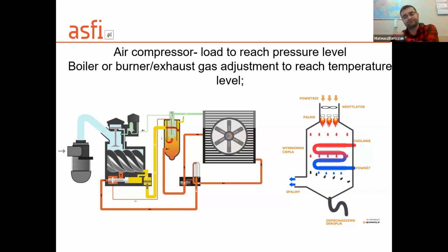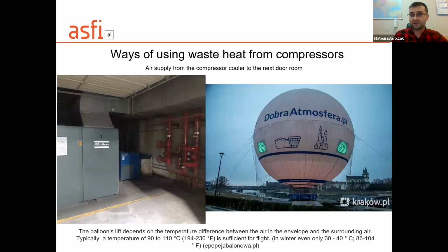And to be honest, I have just said that it is difficult to recover heat from compressors. The compressor doesn't care what temperature you need in this moment. You can get that which is available in this moment, and the compressor doesn't care. It's not the burner, it's not the boiler. It doesn't care how much energy you want to take in this moment. You can take only as much as is possible to take in this moment.